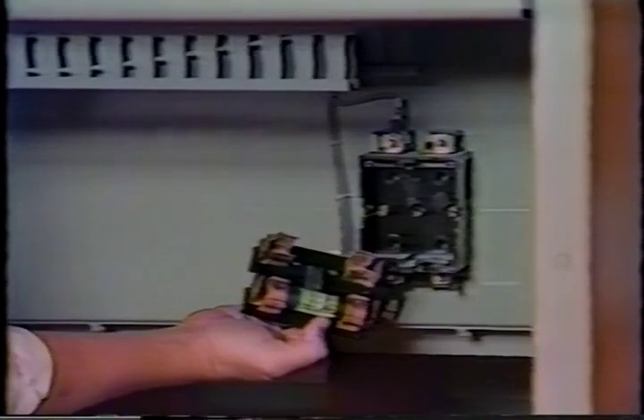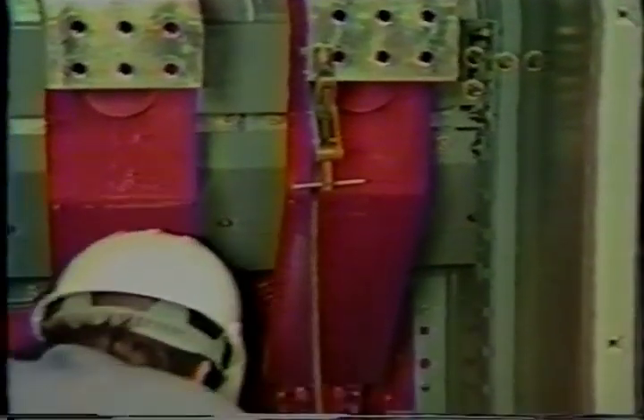Before attempting any inspection or maintenance, be sure that all primary and control circuits have been de-energized and grounded as required, and that proper steps have been taken to be sure that they will remain de-energized until all work is completed. Failure to do so could result in bodily injury or electrocution. When energized, these circuits carry lethally high voltages.